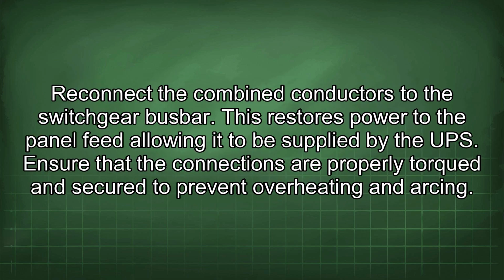Reconnect the combined conductors to the switchgear bus bar. This restores power to the panel feed, allowing it to be supplied by the UPS. Ensure that the connections are properly torqued and secured to prevent overheating and arcing.